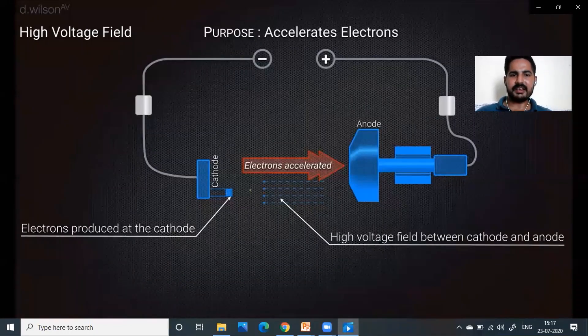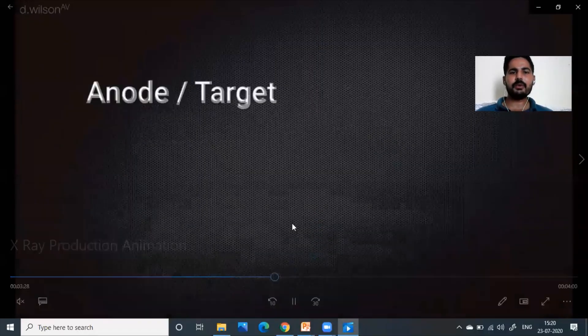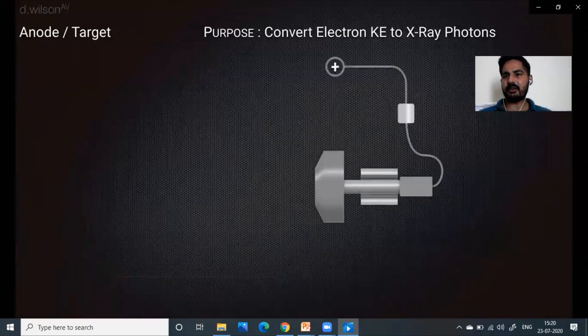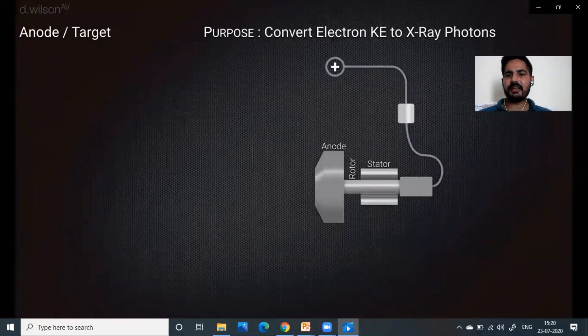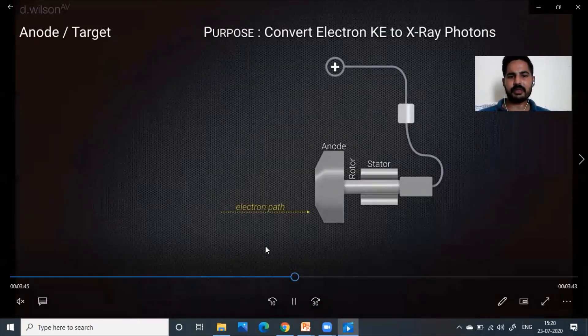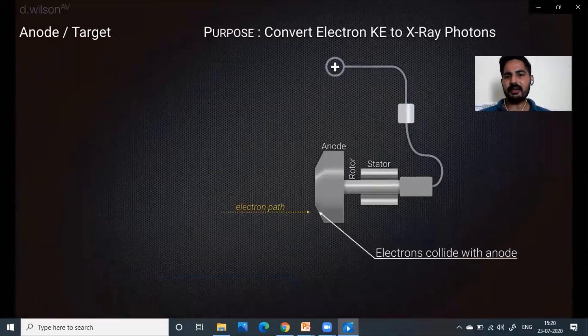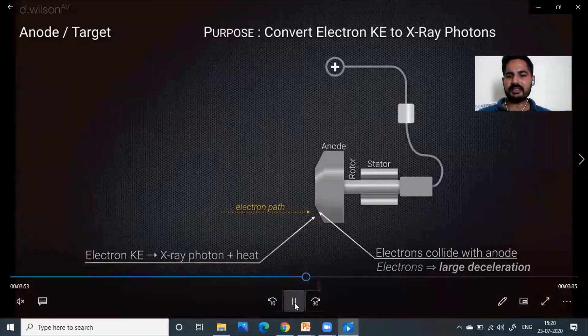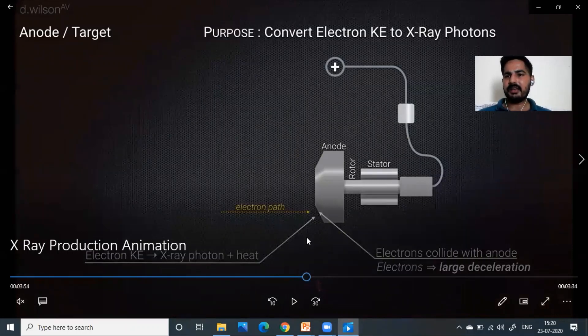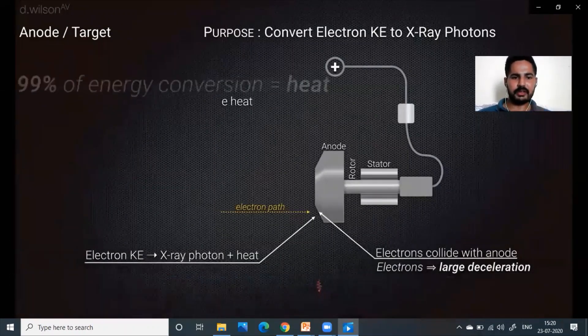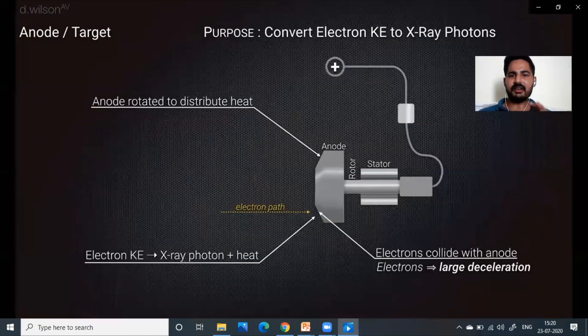Electrons will be accelerated towards the target anode. The purpose of the anode is to convert all the kinetic energy of the electrons into x-ray radiation. Electrons coming at high speed — gained due to the potential difference — hit this metal and produce a lot of heating. The electron collision leads to deceleration; they lose their energy, and that energy is converted into x-rays plus heat.